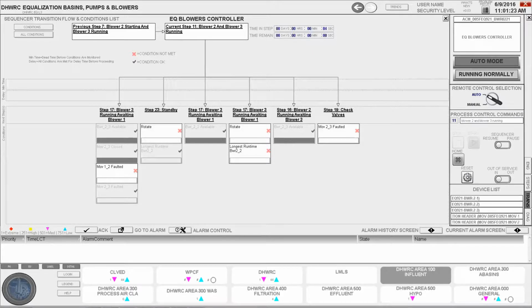During normal operation, the need to see the step progression won't be used as often, but during a not normal situation or system upset, this tool will be invaluable to finding what is preventing us from advancing to the next step or seeing the history that caused the current step. With an aging workforce, operators' experience and knowledge needs to be passed on. Listing the transitions and conditions is one way novice operators can have better process awareness without having to consult the control strategy, saving time and increasing efficiency.